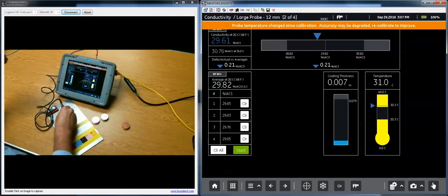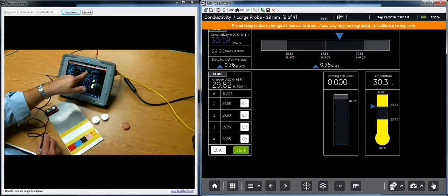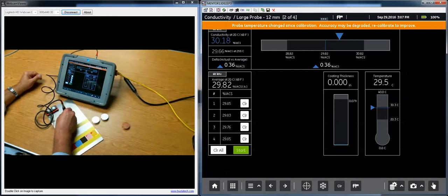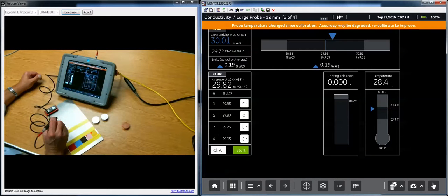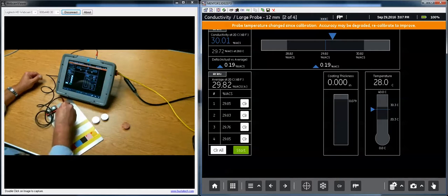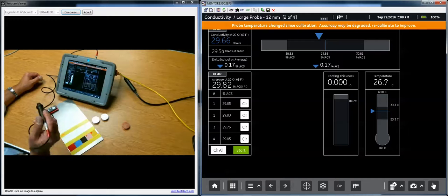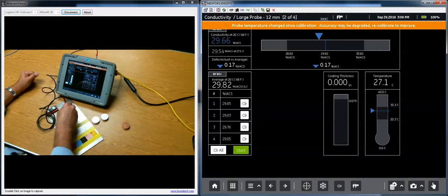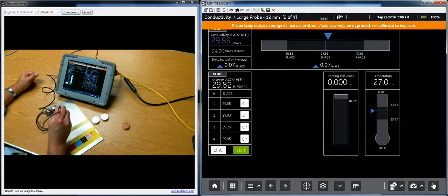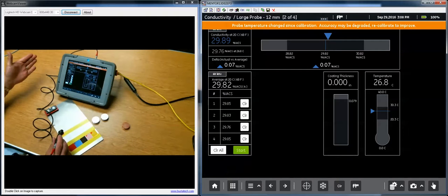If we go back to our aluminum, we take a quick reading. You'll notice I am fairly far away now. Still not outside of the alarm range, but I'm farther away from that center point than we were before. If I put my probe and hold it on the aluminum, it's going to cool down again pretty rapidly. And you notice as it cools, my conductivity reading tends to drift. If I pick the probe back up, it measures the balance point in air again.